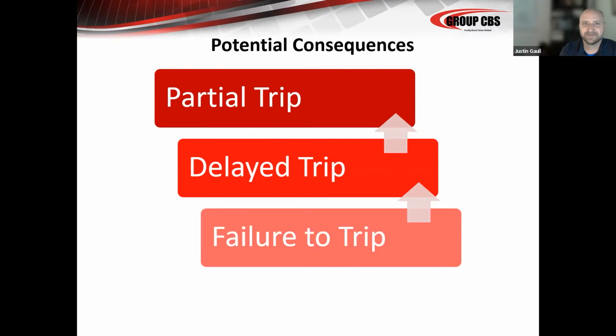Well, it's 100% science and physics. Usually incident energy numbers are higher at 480 volt equipment than they are at medium voltage equipment. Medium voltage equipment has relaying that operates quicker than low voltage trip units do. Usually they're fed through some impedance with cables and distance applications for medium voltage breakers. The other thing with a medium voltage breaker is the gap between the contacts is a lot bigger. So you have all of those components that make incident energy lower most of the time on medium voltage gear than it is on 480 gear.